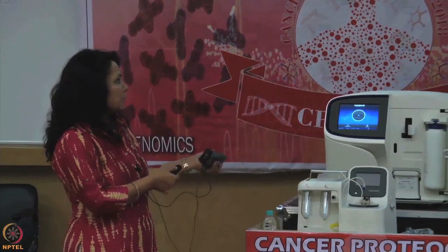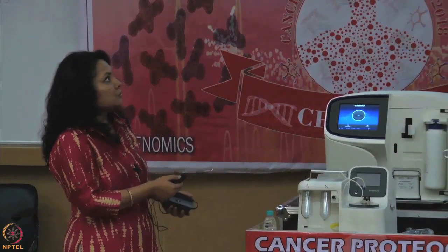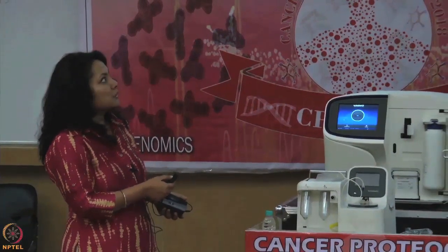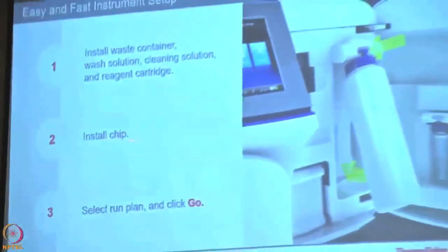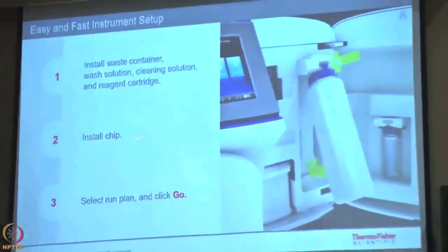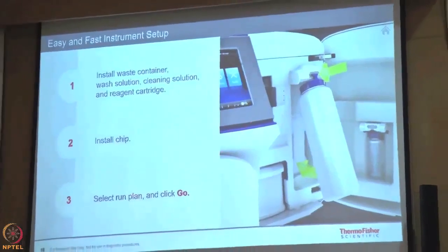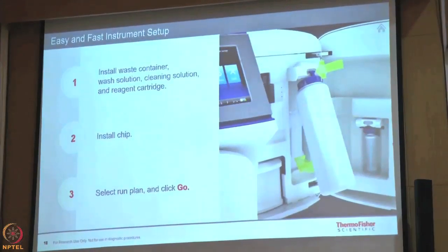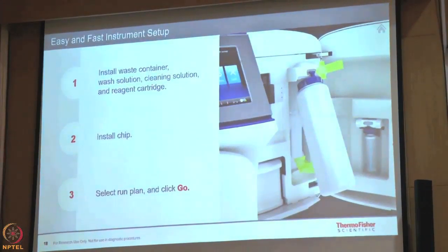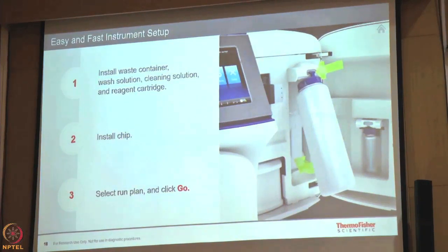To summarize sequencer setup: you install the waste container, wash solution, cleaning solution, and reagent cartridge; you install the chip; you select the run plan and you are good to go. This system also does not need a standalone computer — it can be connected via LAN and operated from anywhere.